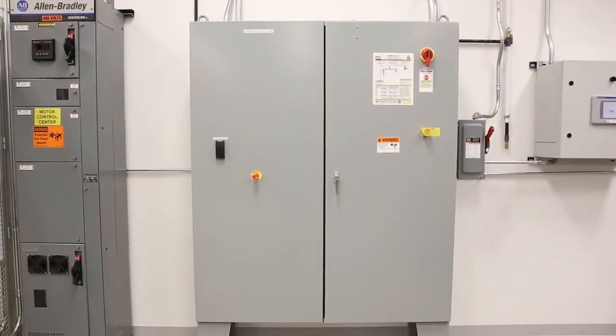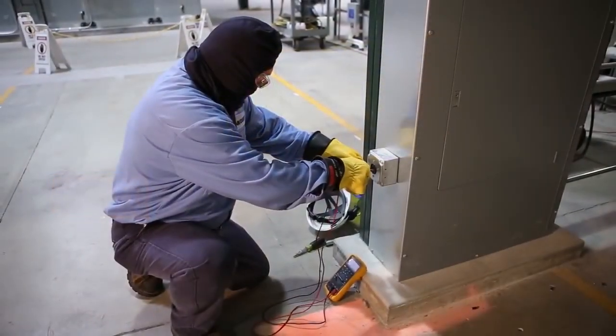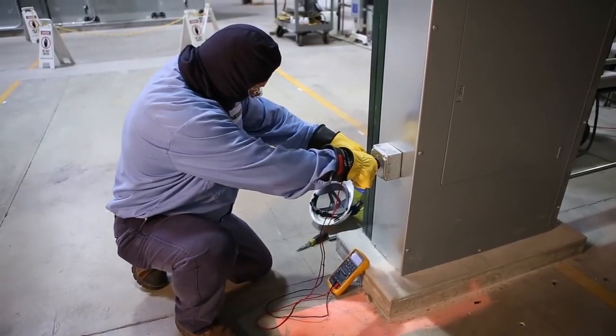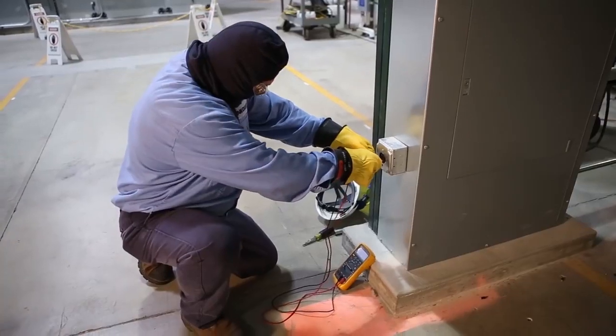VeriSafe is an absence of voltage tester or AVT. This patent-pending device tests for the absence of voltage on electrical equipment. VeriSafe conducts the same test procedure required by NFPA 70E to verify that equipment is electrically safe to work on.